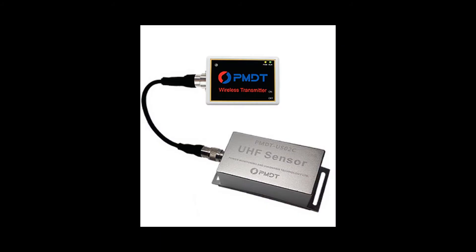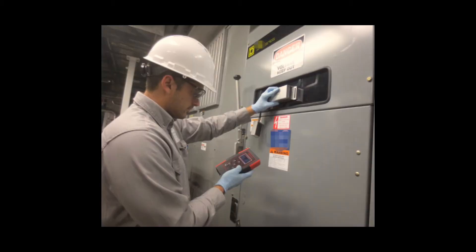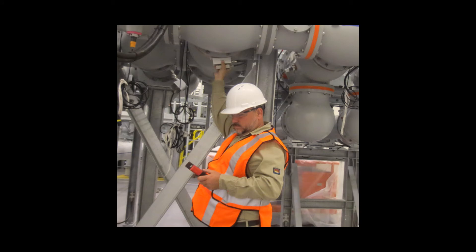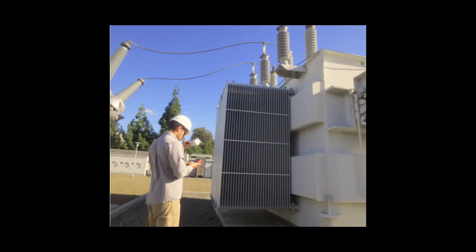The UHF detection method is utilized to detect the ultra high frequency electromagnetic wave signals produced in the electrical equipment. The UHF sensor acts as a special antenna with a response range from 300 megahertz to 1.5 gigahertz. The majority of PD signals have an emission within this range, making this the most versatile sensor. Since the bandwidth of on-site corona disturbance signals are mainly below 300 megahertz, the UHF detection method is effective in avoiding corona disturbances. Its high sensitivity can help determine the PD type as well as its location.